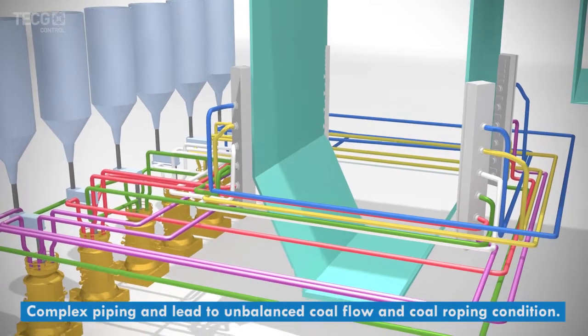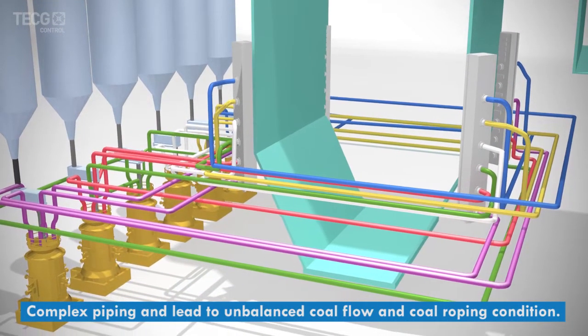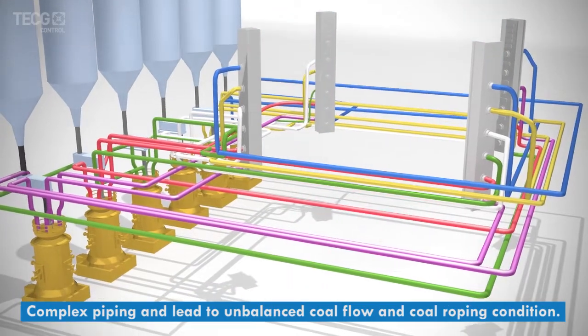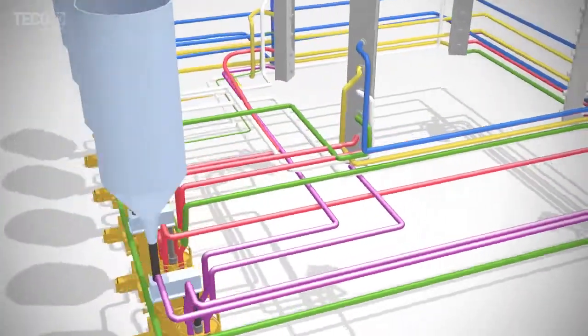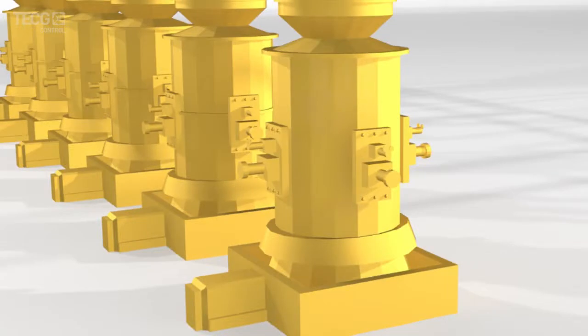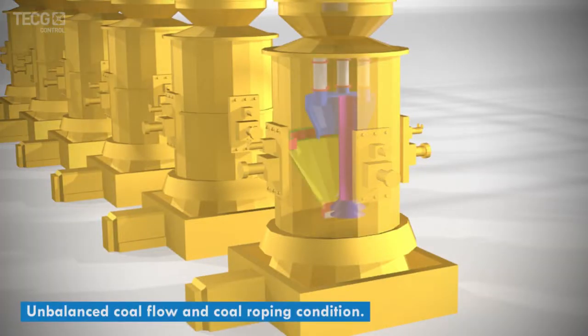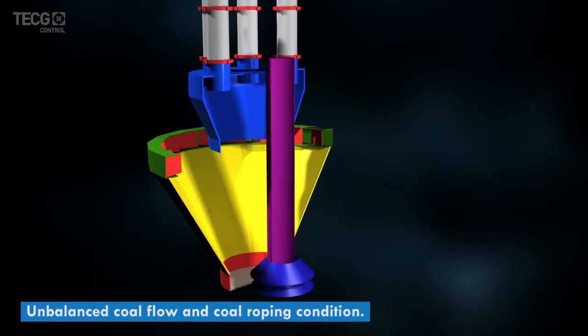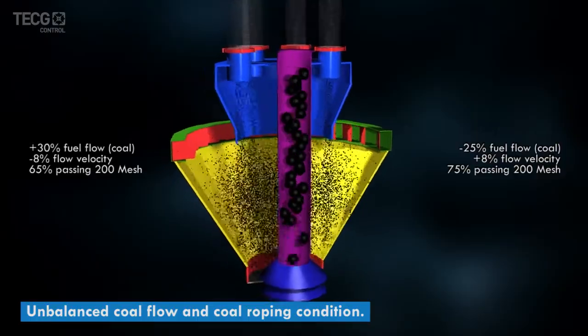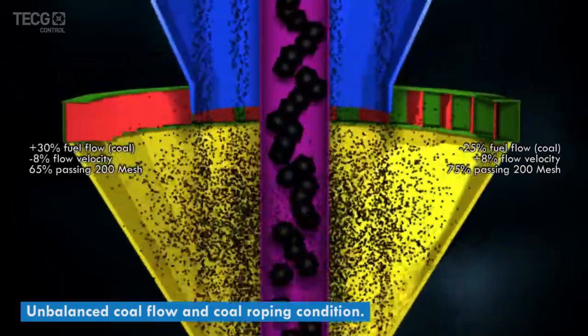In general, the coal mills are installed on one side of the boiler, while the complex coal fuel piping system surrounds the boiler. Due to the complexity of the piping network, the coal fuel supply is often being affected, causing uneven distribution and a coal roping condition.